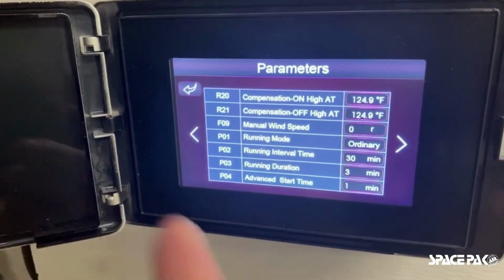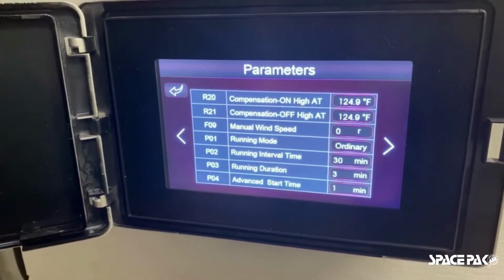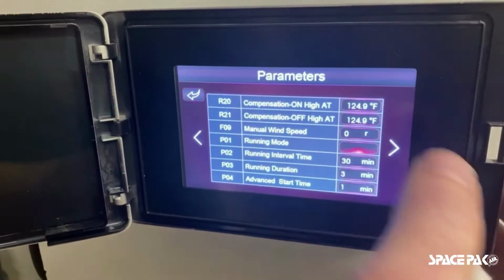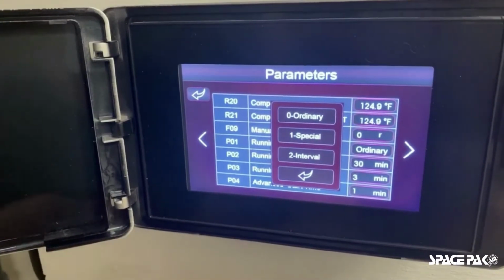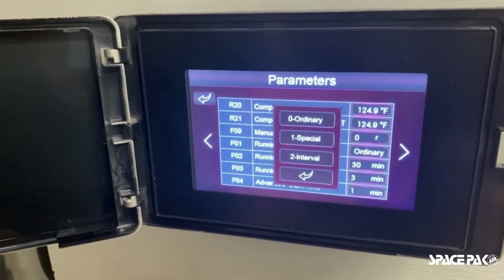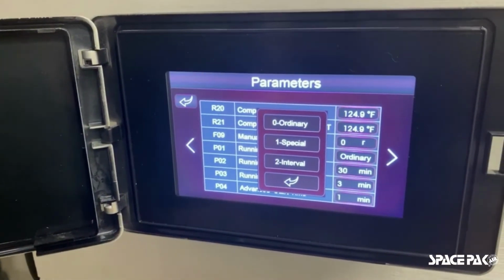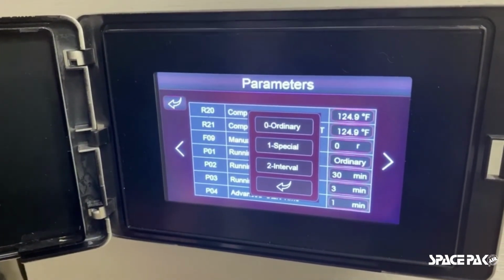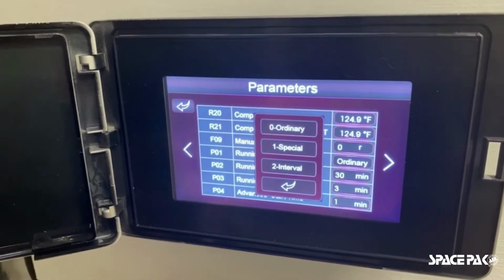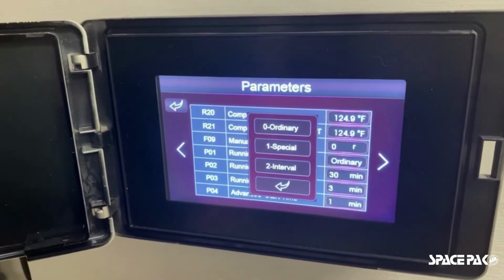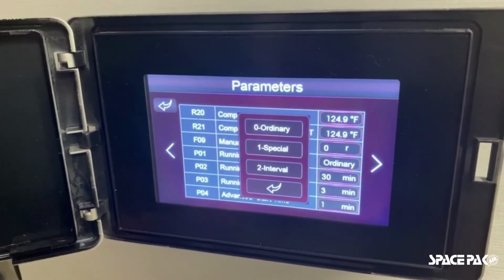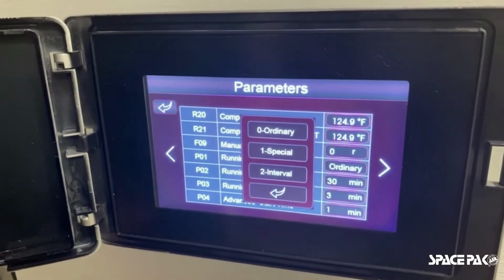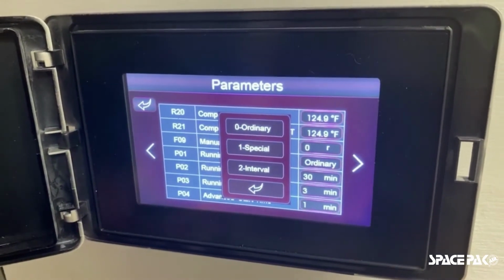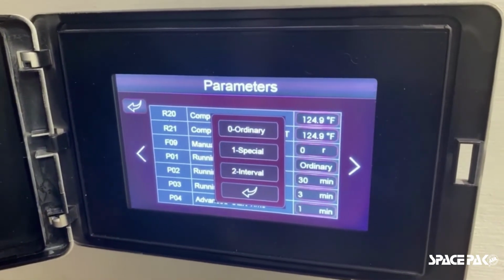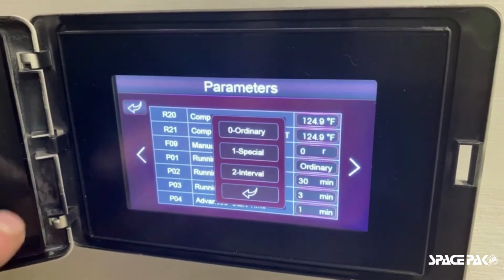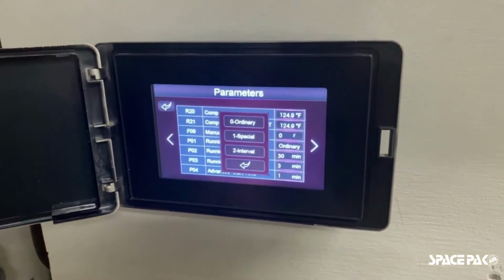Now we have running mode as in ordinary. That would be the mode that the circulator is in. It's either ordinary, special, or interval. We are going to run it in slave mode as ordinary. Those are really the most important first steps in getting your system to run. Everything else, as we can go very deep into this control, is not necessarily required for basic systems, basic heat cool systems.